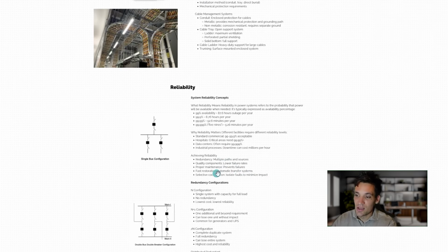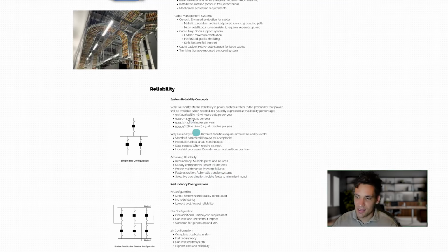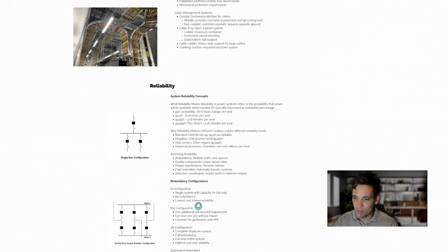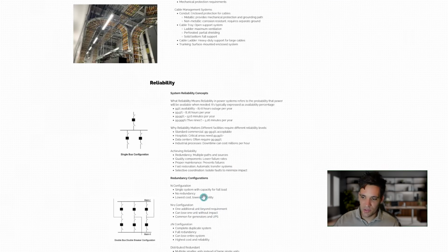So when we talk about redundancy, generally what we talk about is the amount of uptime the system has to have. Again, does it have to have 99% availability, or does it have to have 99.999% availability? 99% availability means you might have like 876 hours of outages per year, when 99.999% reliability would mean you have 5 minutes of outages per year. So they're incredibly different in practice when you talk about them. When we talk about reliability, the general way you'll see it described is whether you have an N configuration, an N+1 configuration, or a 2N configuration. What that means is, do you have secondary reliable components? Say you lose one transformer, do you have a second transformer that could back that up? That's an N+1 or a 2N system.